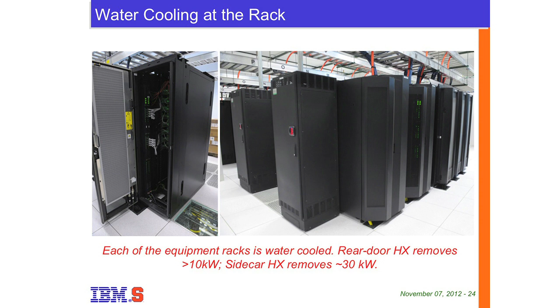There's another type where you put the heat exchanger on the side, and that can remove 30, 35 kilowatts of heat. And I don't have to feed them chilled water at 7 degrees Celsius as you do in a CRAC, a computer room air conditioner. We feed them water at 65 degrees to prevent condensation. So it's above the dew point to prevent any condensation, and they work fine.